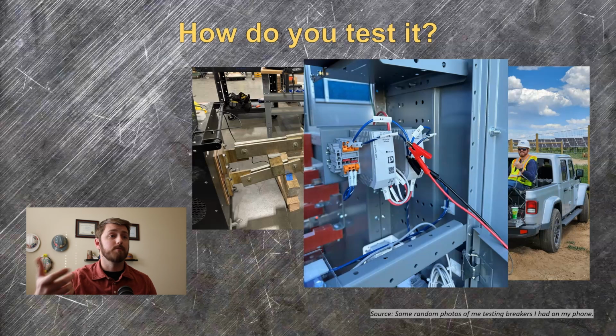So once you've got it powered up, plug it in, turn it on, see what happens. Often this is going to turn on the display of the trip unit, if it has one, which makes it way easier to test anyway. With the maintenance mode switch off, primary inject all of the functions as you normally would: long time, short time, instantaneous, ground fault. Then turn the maintenance mode switch on. If the breaker and system have maintenance mode indicators, like a blue LED or panel light, they need to come on. Square D and Siemens have some goofy contrived system that drives the status output from the trip units back to a communications module, whatever they need to be programmed. That process is unique to each trip unit, so refer to your specific O&M manual for that, but if it has it, it has to work.